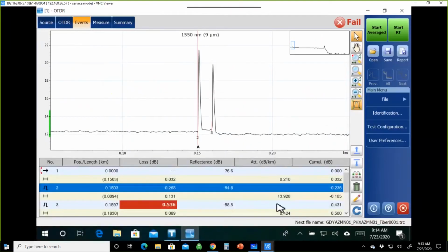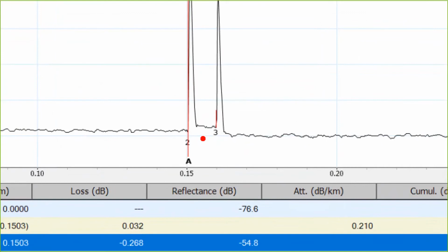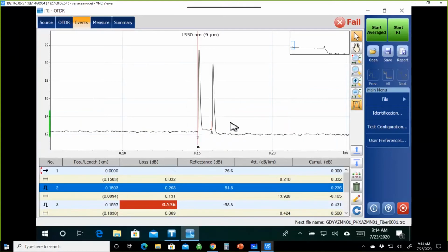So now this explains what we're seeing here: a change in fiber type. If I zoom into that a little bit, you'll see how our power goes up. Gain in power, loss in power. So we have a gainer and a loser. I put that in there just so we can have something to look at. And I also like to draw Batman. Essentially, that's the interpretation of that.